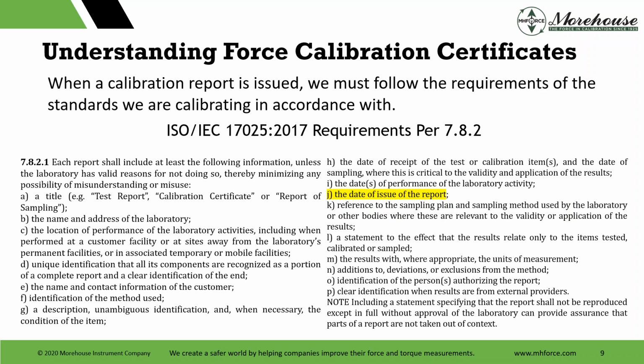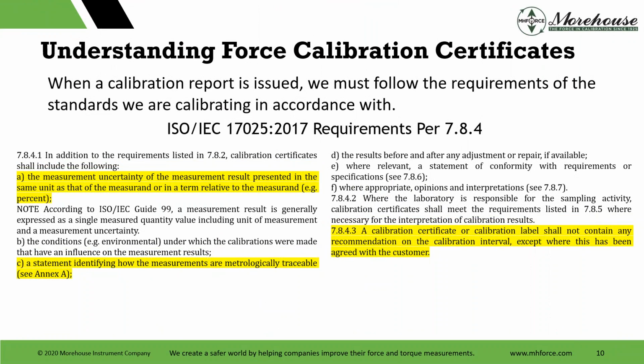I've highlighted it. I think a lot of people probably think it's good enough to just state the date calibrated, but the new standard requires some additional reporting. The measurement uncertainty result shall be presented. That should be on all certificates. There must also be a statement identifying how the measurements are metrologically traceable. And then we have 7.8.4.3: a calibration certificate or calibration label shall not contain any recommendation on calibration interval, except where this has been agreed with the customer.